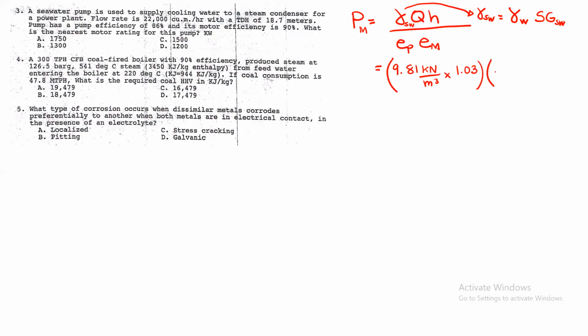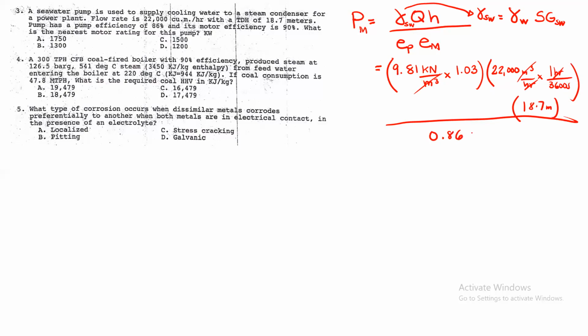Then Q, what is our Q? 22,000 cubic meters per hour, times 1 hour per 3,600 seconds, then multiplied by 18.7 meters. The meter cubes cancel, and kilonewton-meter per second is kilowatt. Then we divide by the efficiency of the pump, 0.86, then the efficiency of the motor, 0.90. So what we get here, guys, is a motor power of 1,500 kilowatts.